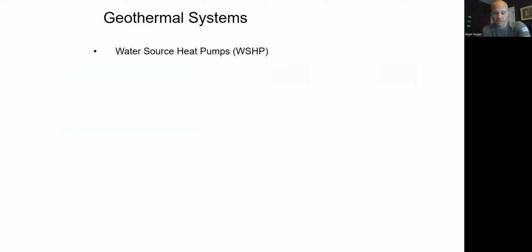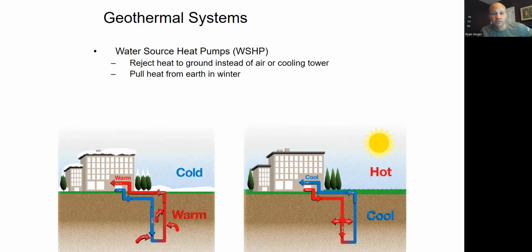You can also do this stuff with geothermal. So a geothermal system is a water source heat pump. It's not anything different, right? It's obviously being set up differently and piped a little differently, but it's the same idea. It's a water source heat pump. Instead of sending its heat into a cooling tower, it sends its heat into the ground in the summer. So no cooling tower on the roof typically. It sends all the heat into the ground. The ground cools off my water and sends it back.